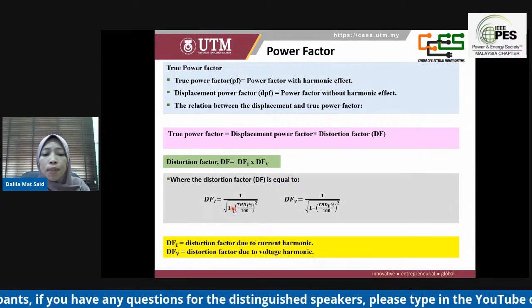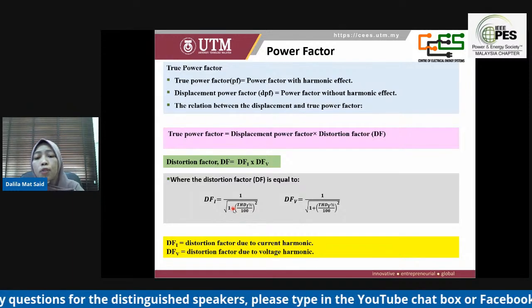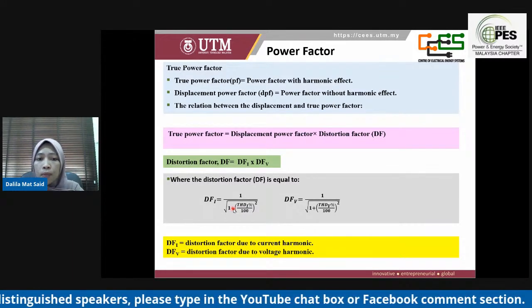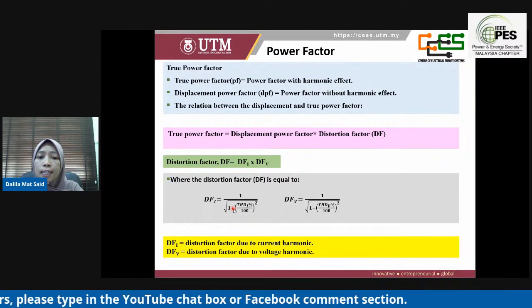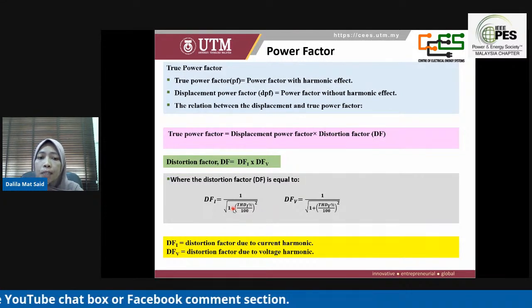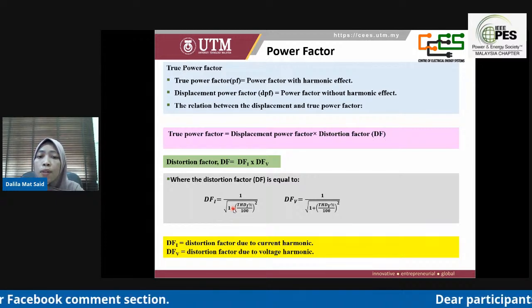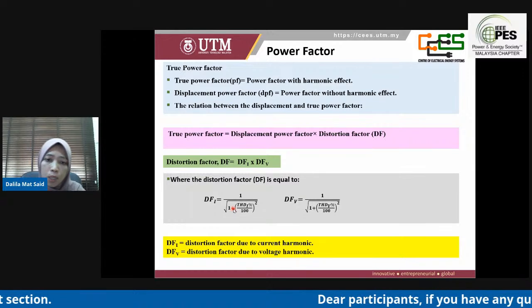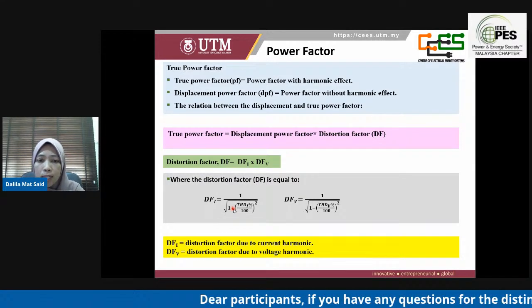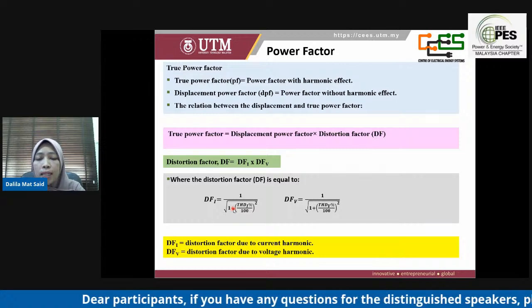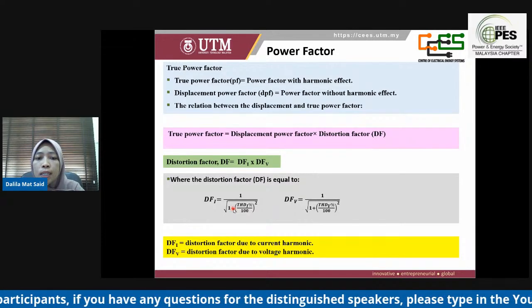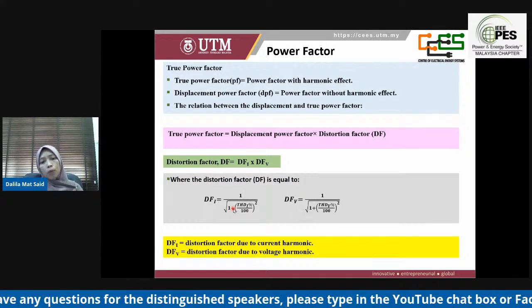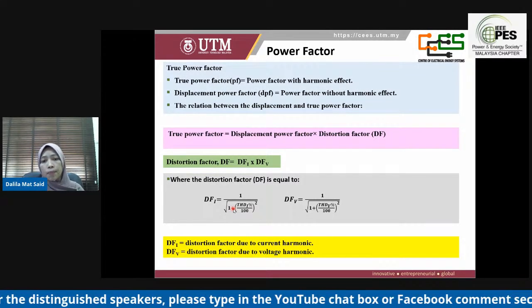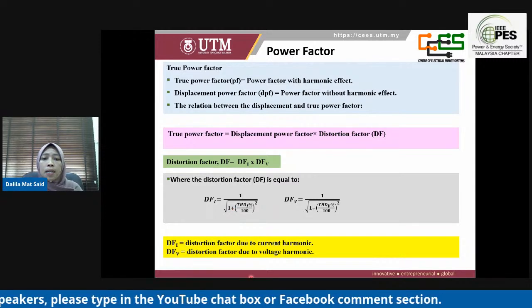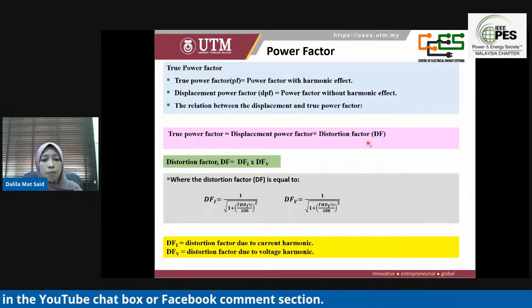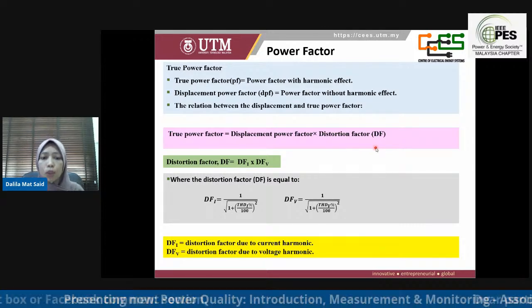Another important index when dealing with harmonics is the true power factor. True power factor is the power factor that considers the harmonics. Displacement power factor is the power factor without the harmonic effect, which we calculate from cos theta or P over S. That's what we call the displacement power factor. As for the relation between the displacement and true power factor, the true power factor can be calculated by multiplying the displacement power factor with the distortion factor.